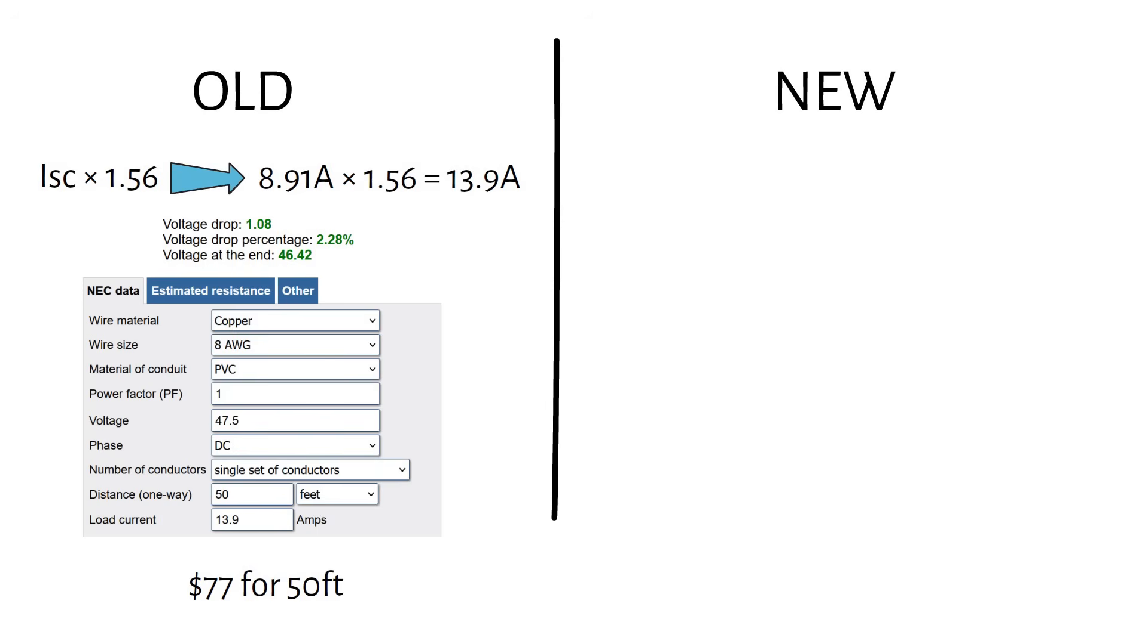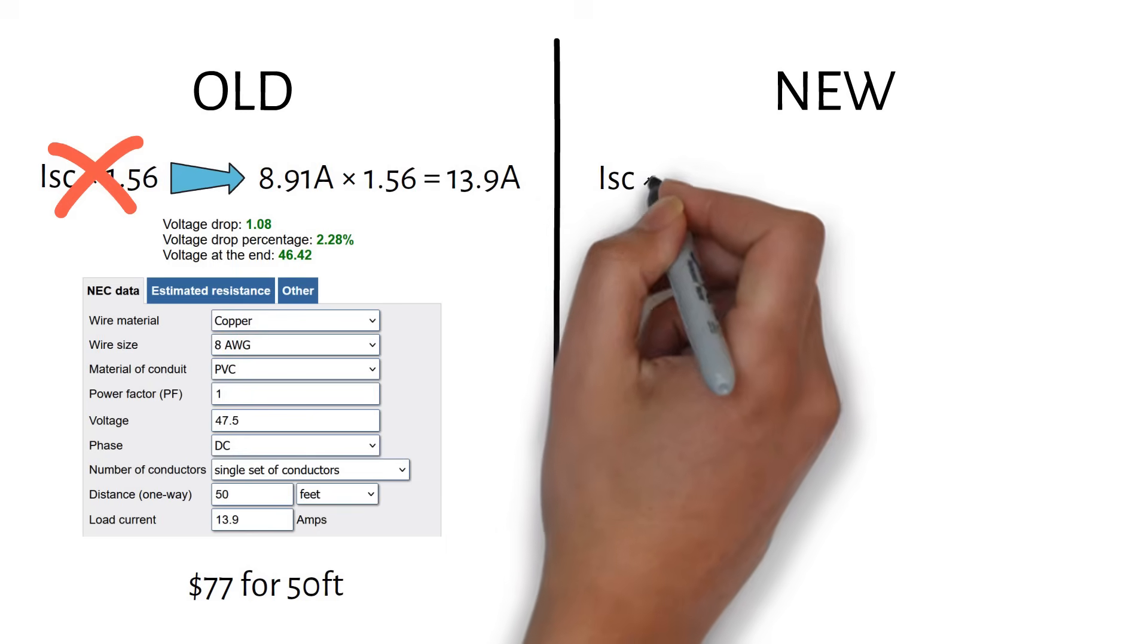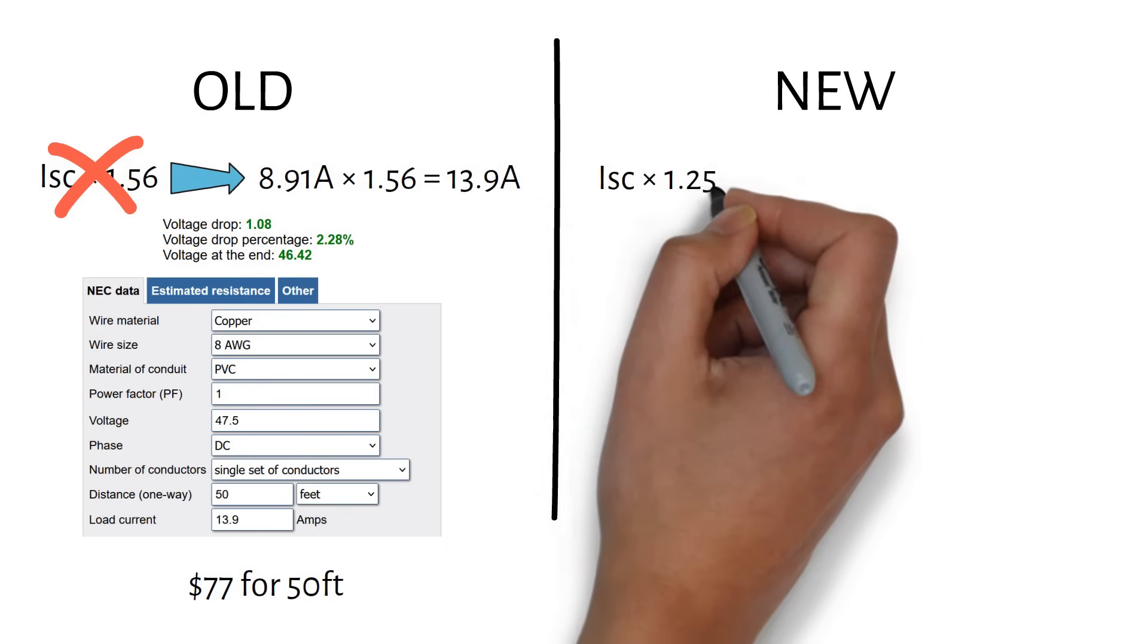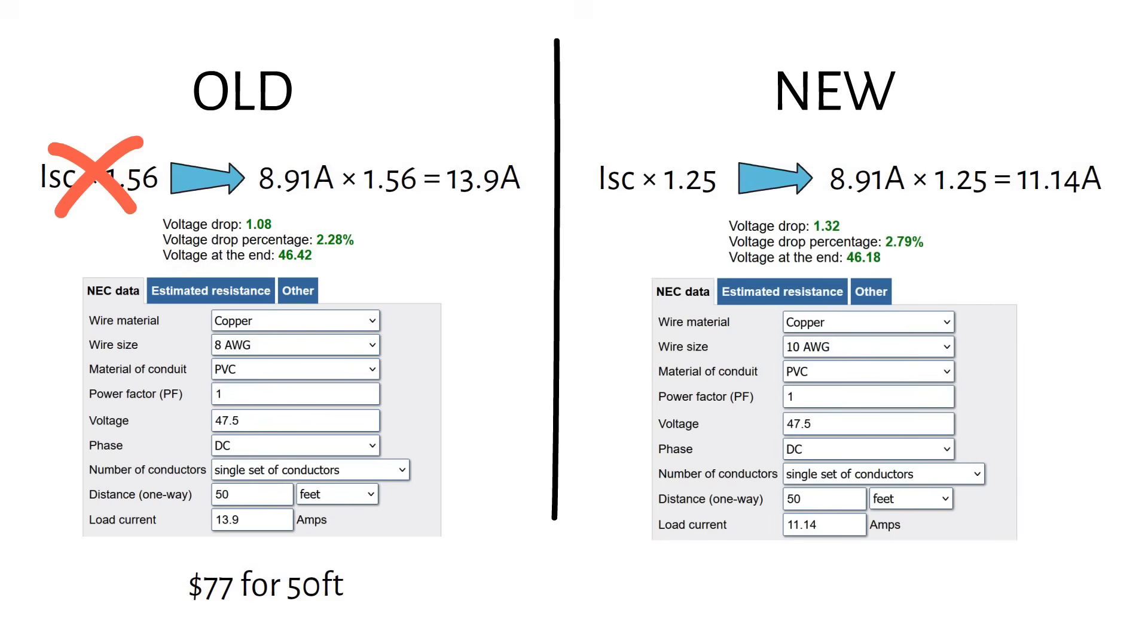Now let's repeat the voltage drop calculation with the new method. Instead of using the ISC times 1.56, we're using ISC times 1.25. That's because in a voltage drop calculation, you don't need to add the additional safety factor for direct sunshine. So for this example, it's 11.14 amps. All the other numbers stay the same.